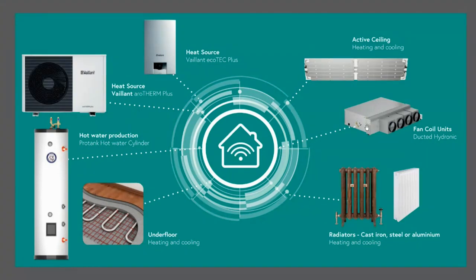And it can be then put in combination with, say, an underfloor heating system or a radiator system in different parts of the house. And then we also do what's called active ceiling, which is radiant ceiling panels, which are very effective at heating and cooling and don't require the same infrastructural investment of putting, say, pipe in a construction slab. And they can be piped out through the roof space. So they offer an alternative to get that sort of high quality radiant style heating to a home.